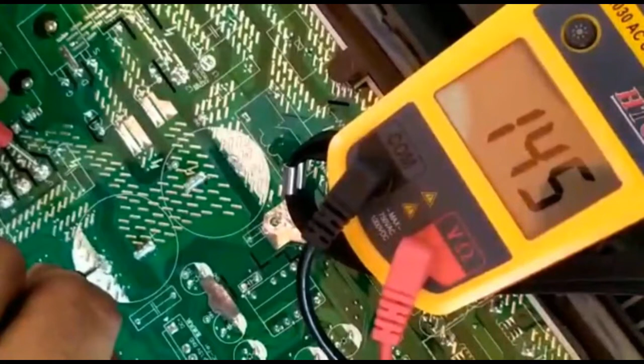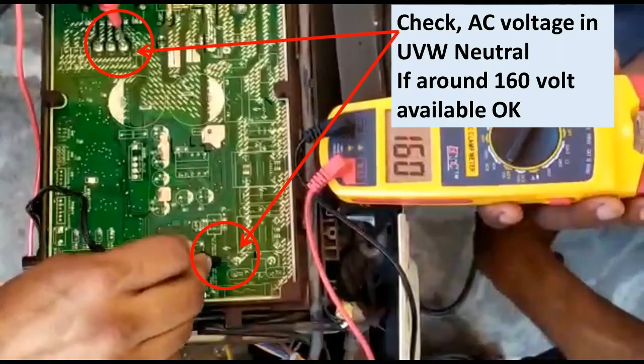Then we have to check the output for the compressor. For the compressor we have U, V and W, and at these points we have to check the DC voltage, and we can also check the AC voltage. For checking the DC voltage, we have to place one probe of the clamp meter on the capacitor negative point and the other on the U point, then V point and then W, and in all 3 we will get the same DC voltage. It will be around 150 to 160 volts.